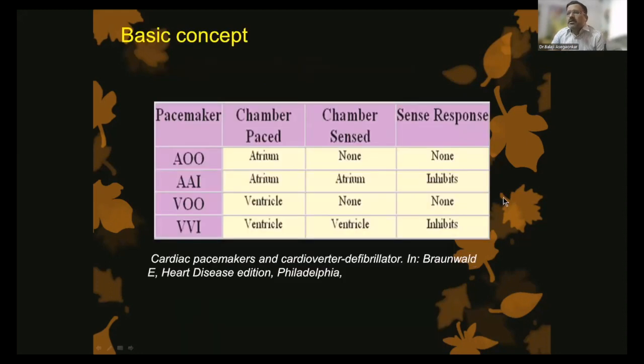This pacemaker has a nomenclature concept. Suppose we put a VVI pacemaker: the first letter indicates the chamber paced, the second letter indicates the chamber sensed, and the third letter indicates the sense response, whether it is inhibitory or stimulatory.